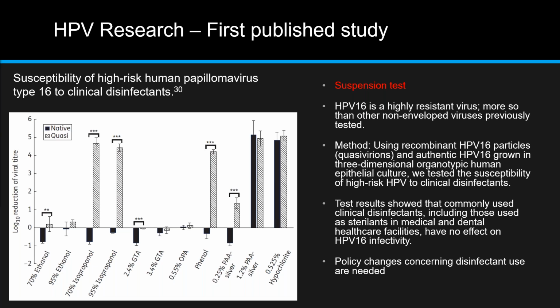And you can see some of the differences with the surrogate particles, especially if you look at isopropanol. The surrogate particles were clearly deactivated or killed by isopropanol, but the native HPV, it had no effect on it. It did not deactivate or kill the native HPV in any way. The other thing to point out here is if you look at GTA and OPA, this is what I mentioned before, these have been classified as high-level disinfectants. But what we found was that neither GTA or OPA was able to kill human papillomavirus. So again, those definitions came out before anybody could test human papillomavirus. So you also have to consider, when you're looking at your evidence-based practice, has that high-level disinfectant been tested against native infectious HPV?